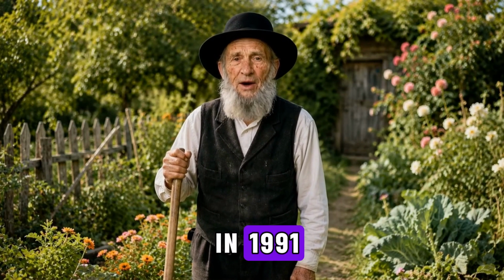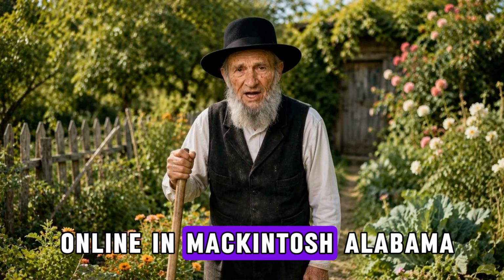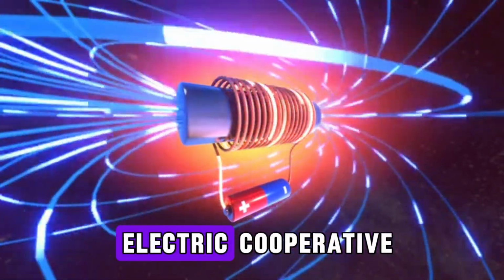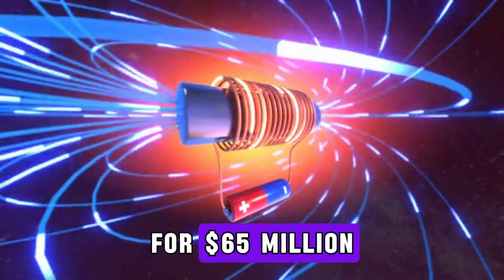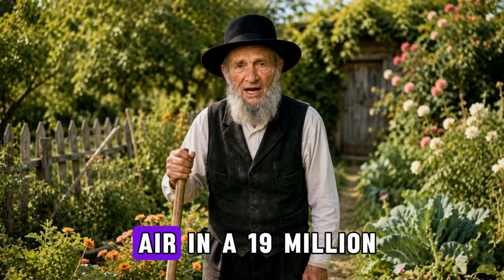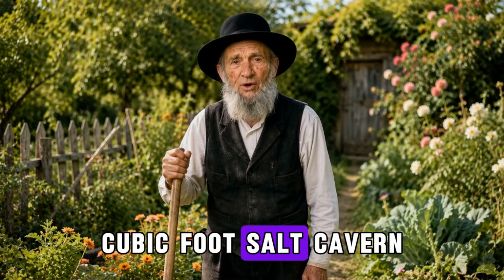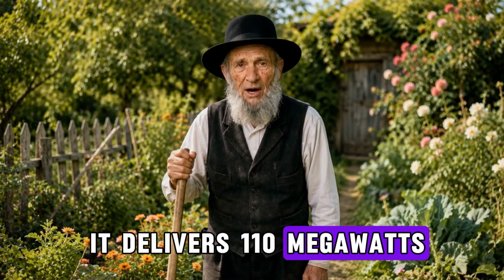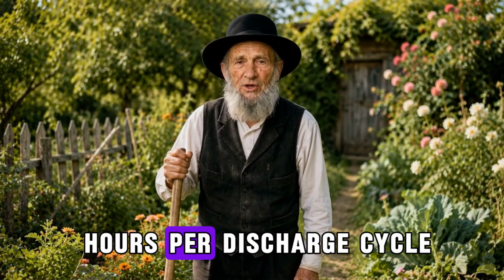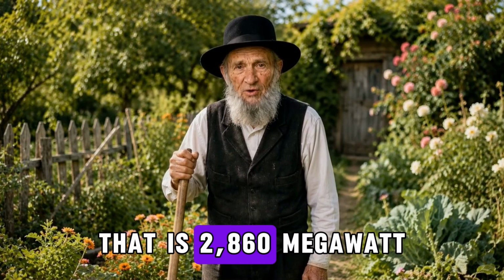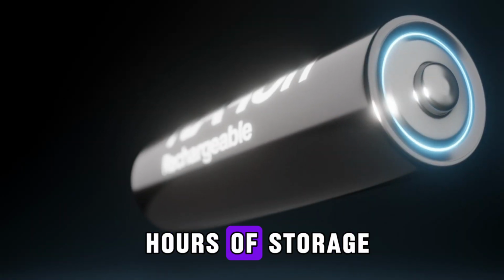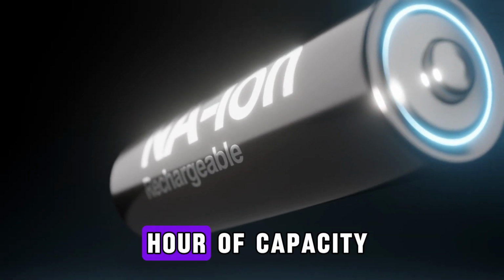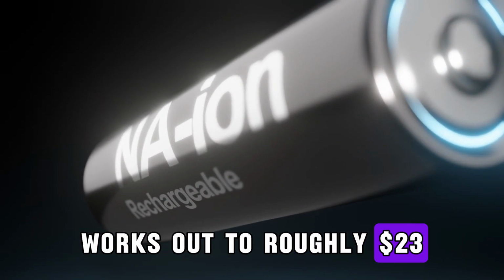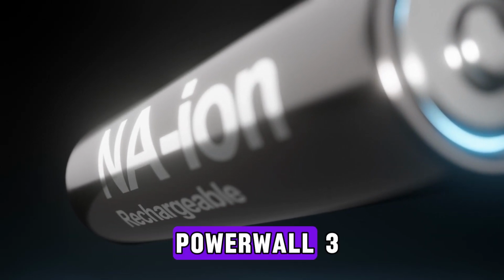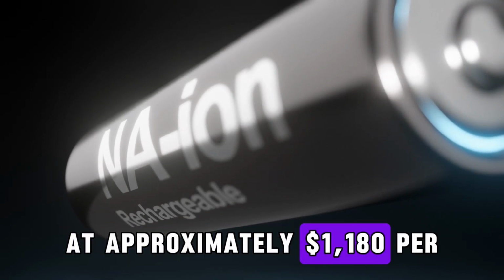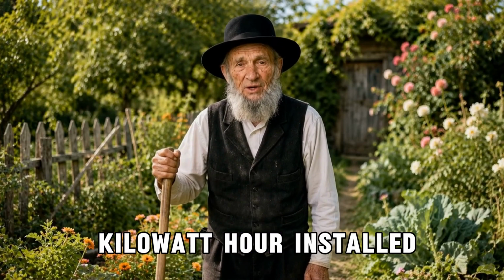In 1991, a second plant went online in McIntosh, Alabama. Built by the Alabama Electric Cooperative for $65 million, the McIntosh facility stores air in a 19 million cubic foot salt cavern. It delivers 110 megawatts for up to 26 hours per discharge cycle. That is 2,860 megawatt hours of storage. The cost per kilowatt hour of capacity works out to roughly $23. Compare that to the Powerwall 3 at approximately $1,180 per kilowatt hour installed.